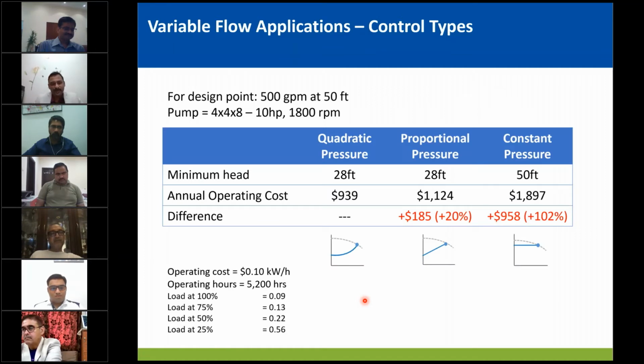Now, if you compare the energy consumption of all three control strategies, we will baseline the quadratic pressure control curve as the best practice, and we will look at the energy consumption of the other two control strategies. The proportional pressure control curve would still consume 20% more. And if you have a constant pressure control or pump room mechanical sensor, you often see at least 100% more energy consumption compared to the best practice.